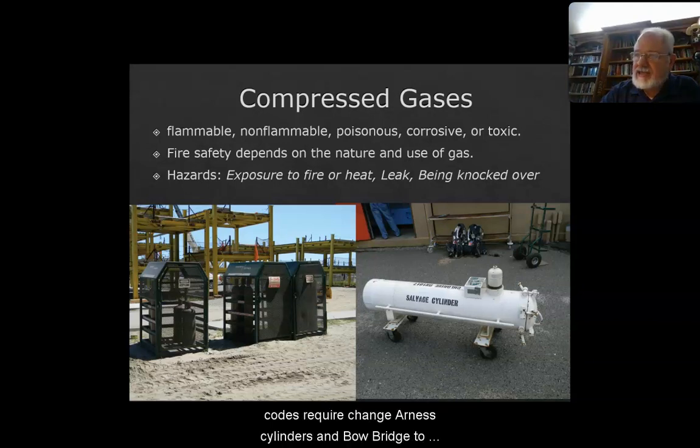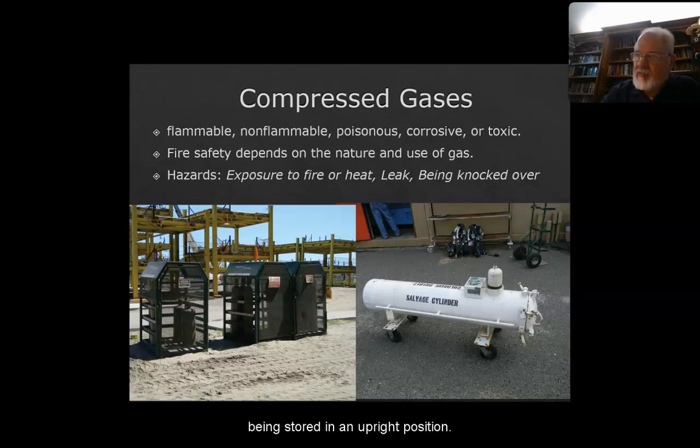Codes require chains or nest cylinders and valve hoods to be in place when the cylinder is not in use. It should always be stored in an upright position, with an appropriate pressure regulator, and no Teflon tape for metal-to-metal contact. All high-pressure cylinders of compressed gas must comply with DOT and ICC regulations for pressure relief valves, and hydrostatic testing of the cylinders is conducted every 5 to 12 years.